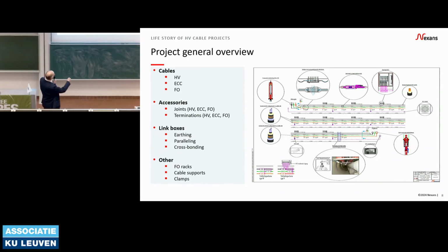Also, on the electrical point of view, you see here we have a transposition between phases. It doesn't seem like a problem, but if you do not manage that correctly at the right time, your jointers could mix the phases and make a reverse order, and then you have a problem for letting your cable link work properly. So this is also an important step to know your scope: what do I have to supply, what do I have to install in my project?